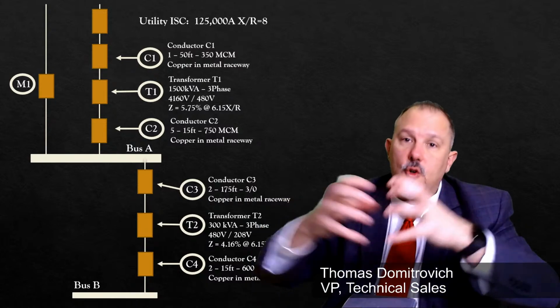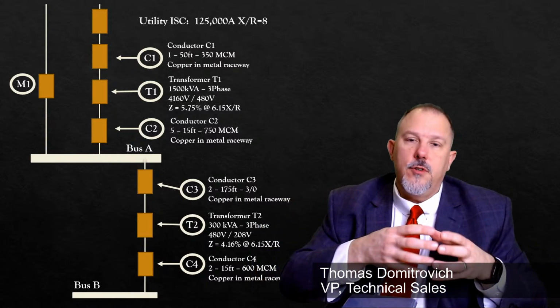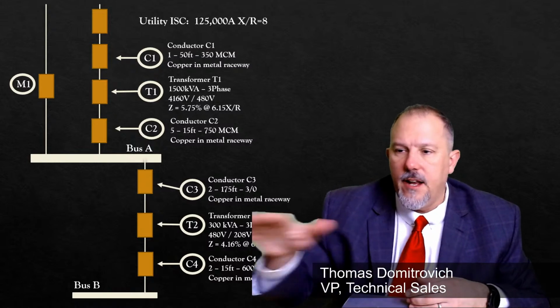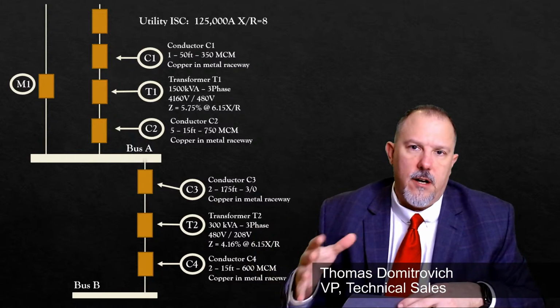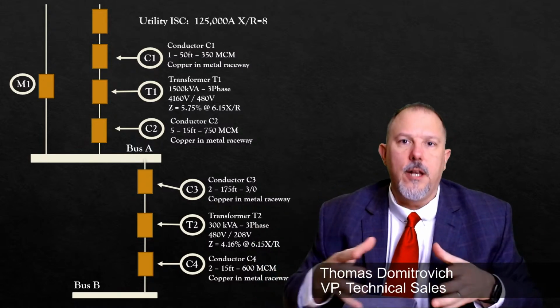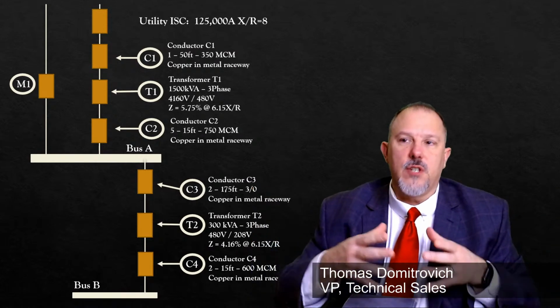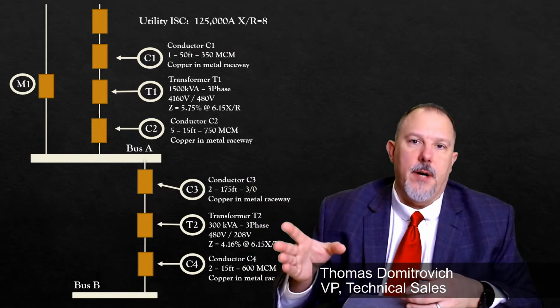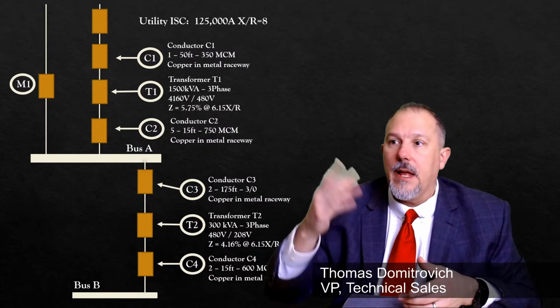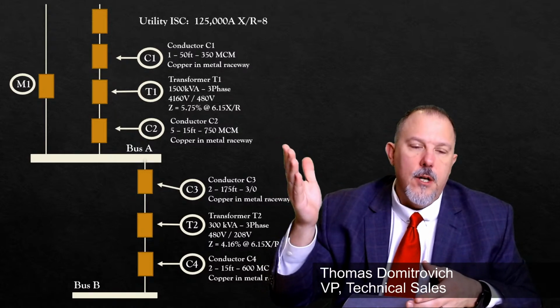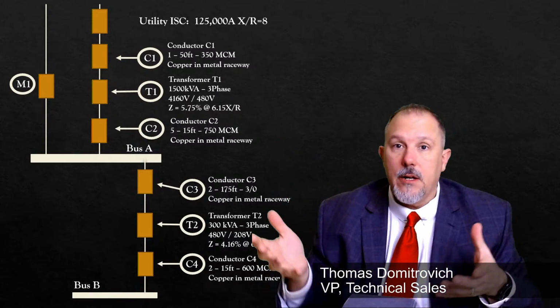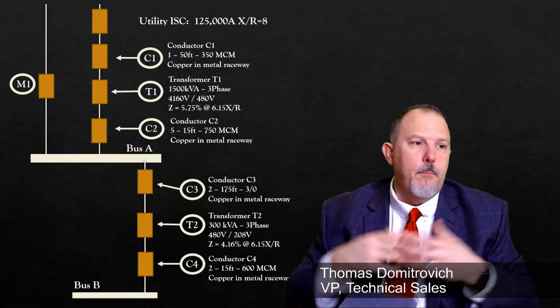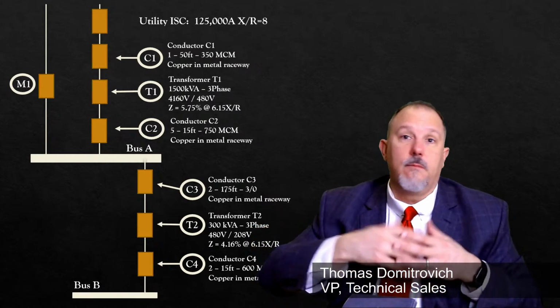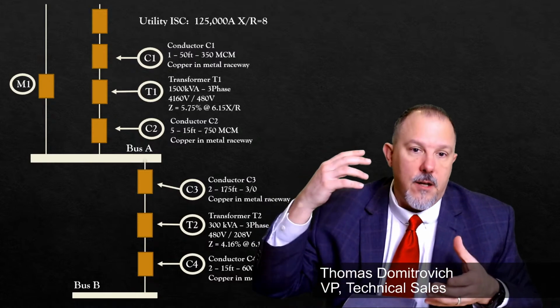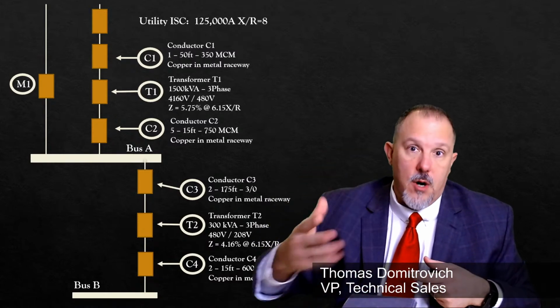Because what we do is we group small motors, and what you could do is say there's a lot of compressors out there, there's a lot of 25 horsepower motors or whatnot. You basically sum all of those up and just slap it on a bus. So like that motor 1 that we have here, that's 300 horsepower of motor. That could be a bunch of 25 horsepower motors that I just sum them all up and slap it on bus A and model it that way.